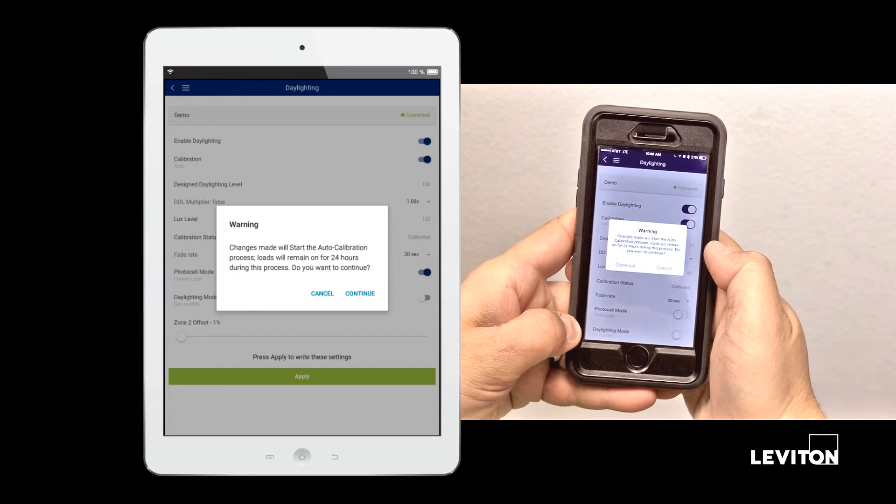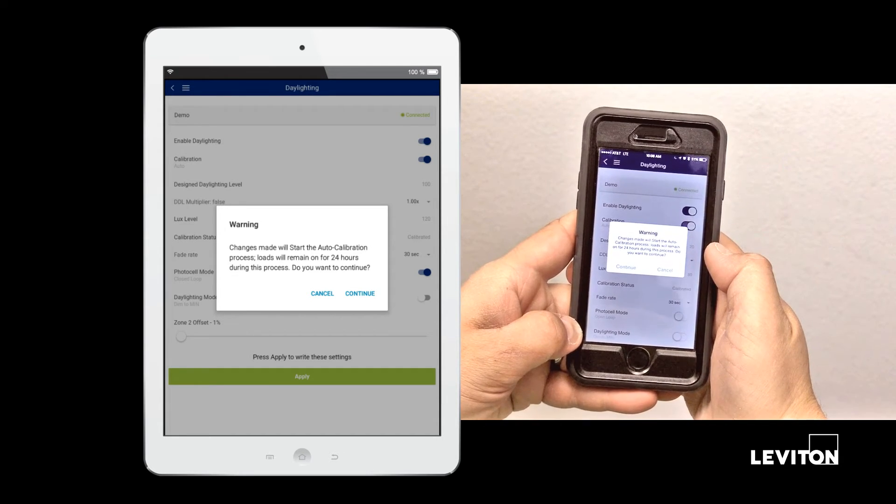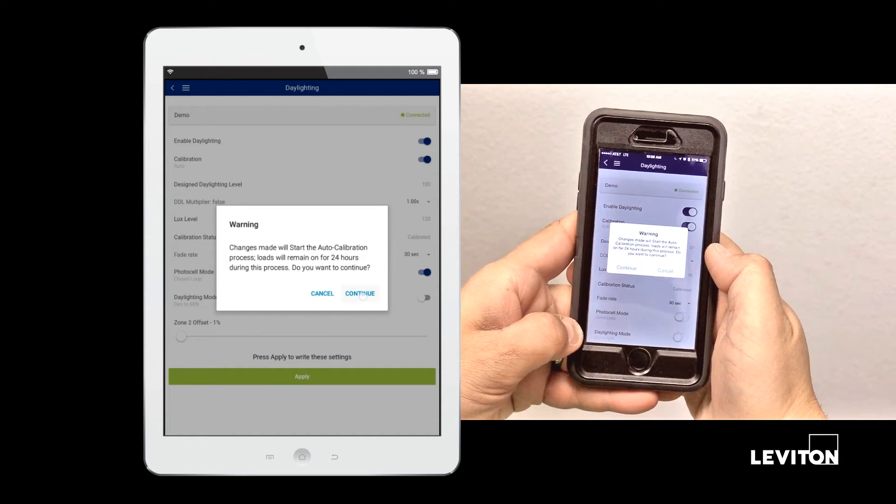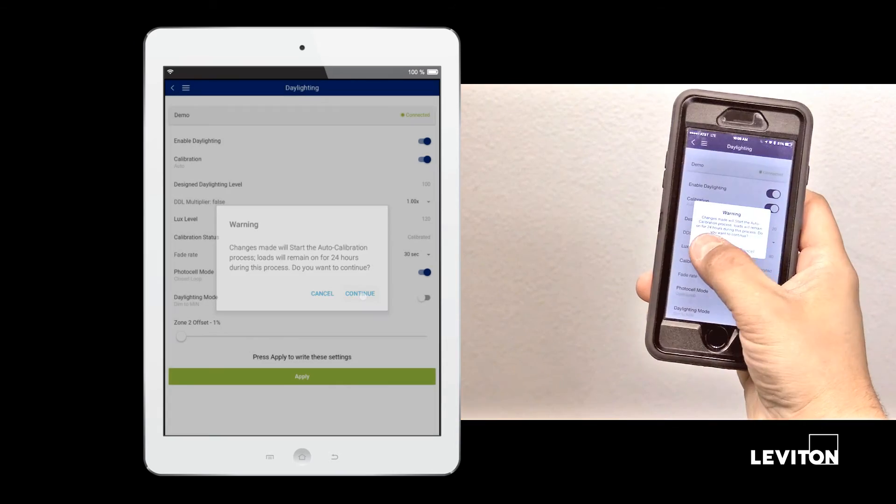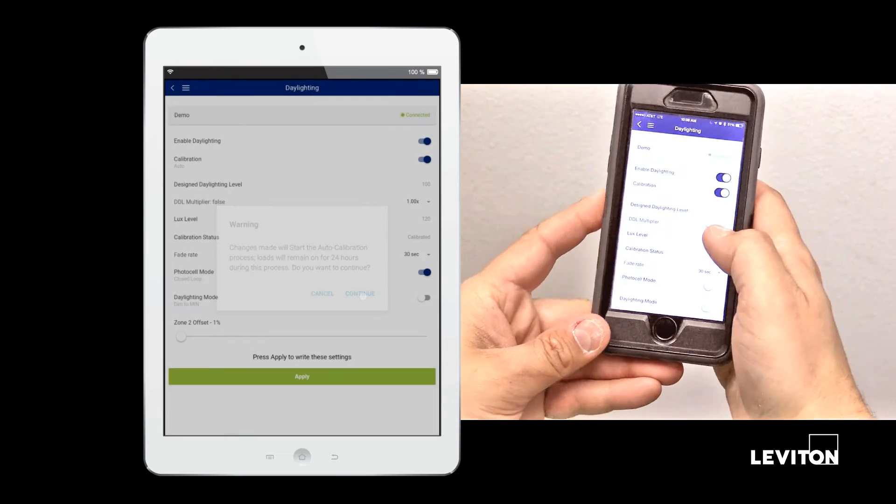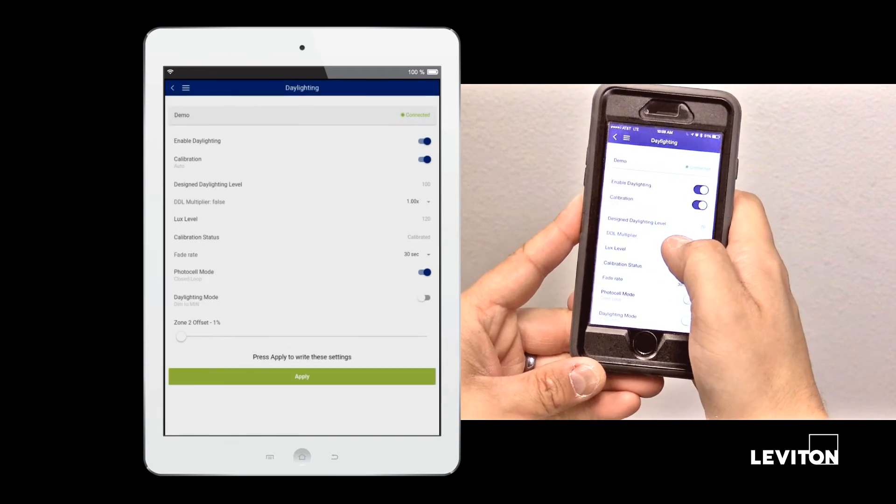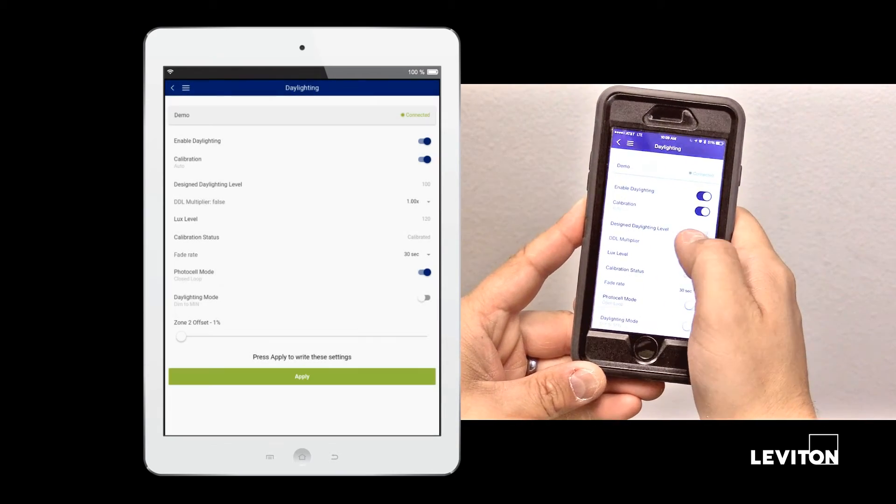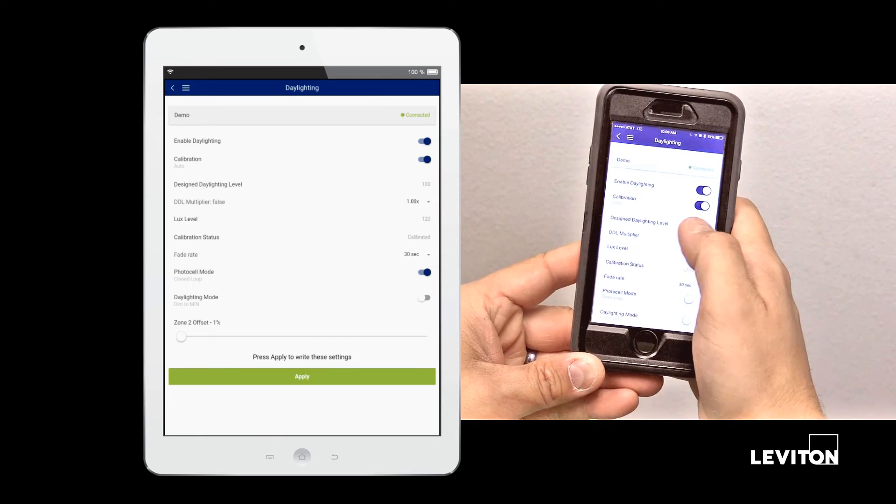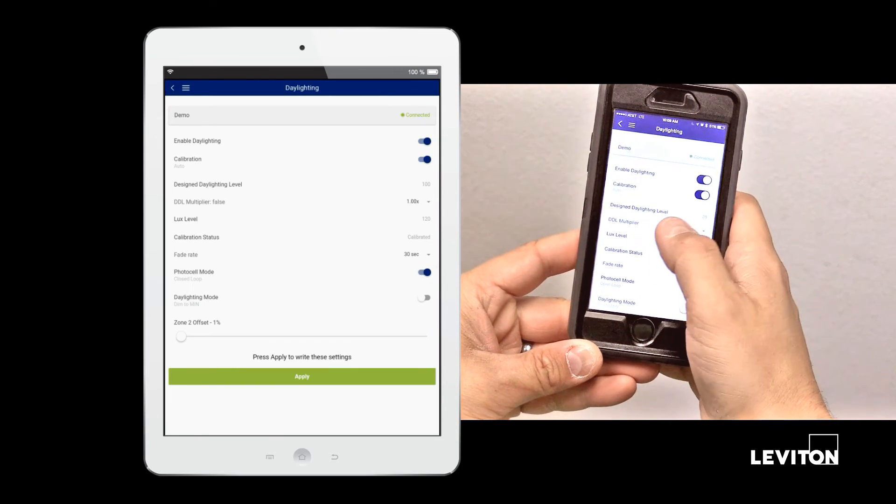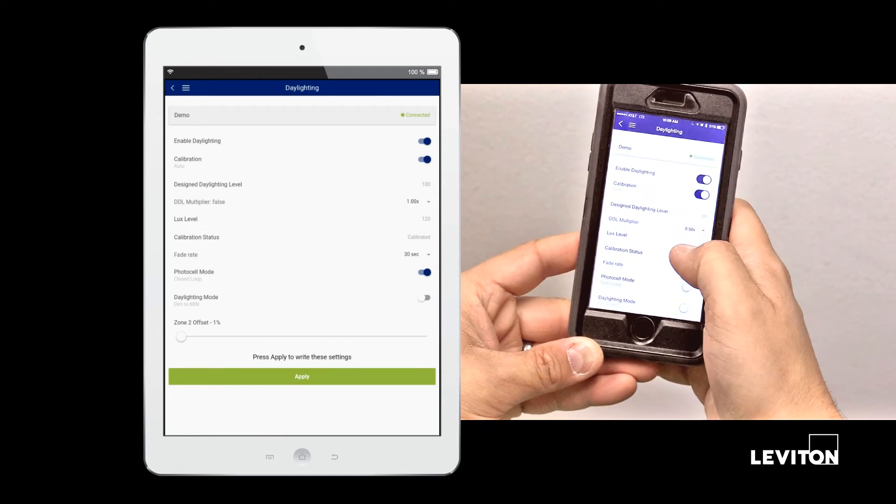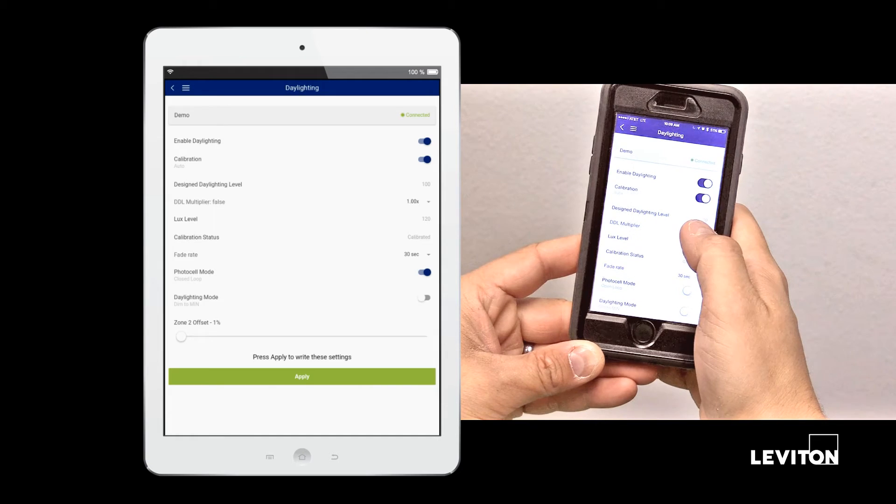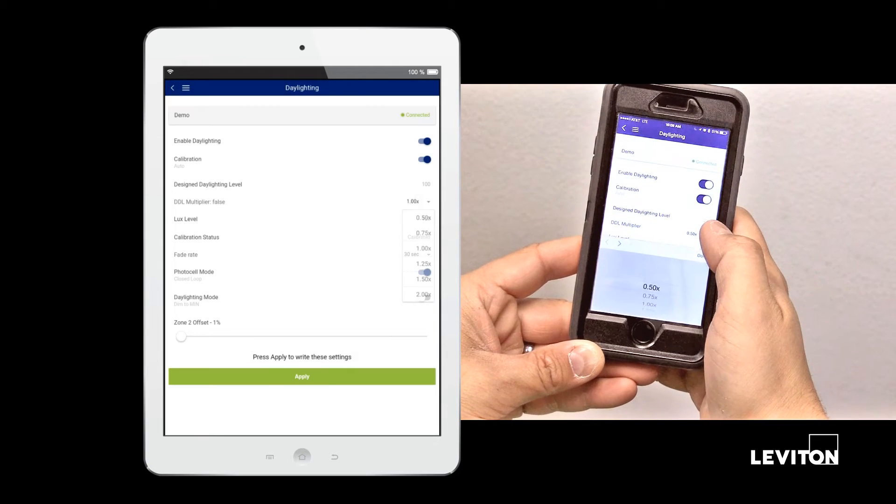During this time, the lights will remain on at 100% while the PRC captures and logs light levels within the space. In the auto calibration mode, we cannot manually adjust the design daylight level that is set by the auto calibration process. We can adjust the DDL multiplier.